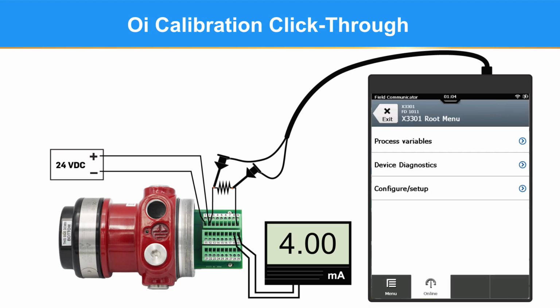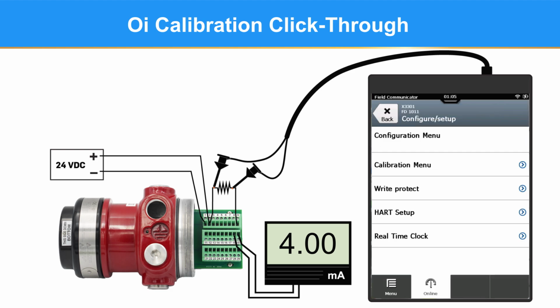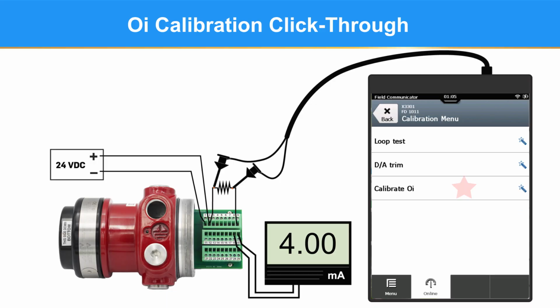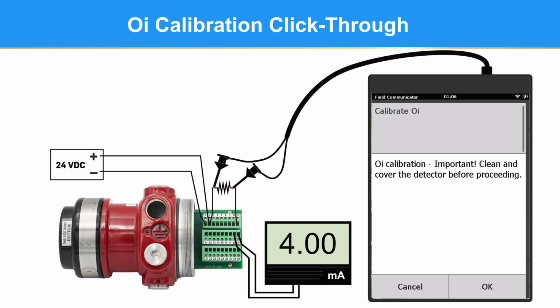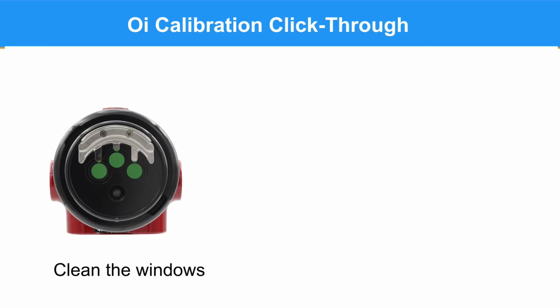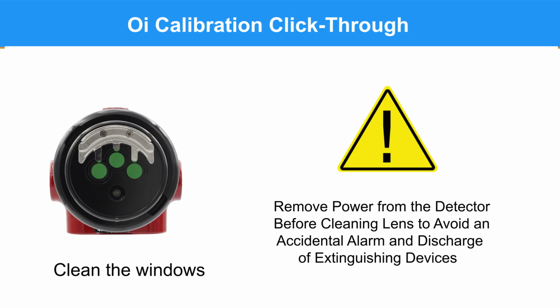We'll start by clicking Configure Setup, then Calibration menu, then Calibrate OI. The procedure starts with a very important warning. You must clean the windows and put the black cap over the windows before starting the OI calibration. And just in case you didn't know, you should remove power before cleaning the windows to keep the detector from possibly going into alarm due to the motion of your movements blocking and unblocking IR energy.